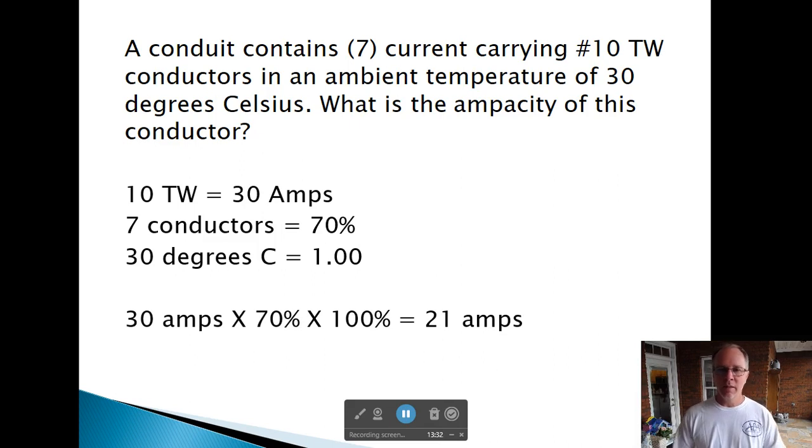Most of your questions will be this type of question. I know you're students and I'm just trying to get you to flip the pages and start understanding the National Electrical Code on the ampacity side. There's tons of different things and more details. Things like underground temperatures are basically constant, so there's no de-rating. If you're going up a wall, if it's no more than 10 feet you don't have to de-rate. But if it's more than 10 feet, then you have to start de-rating. If we can get you these three charts, you've got a good base start on ampacity in the National Electrical Code.